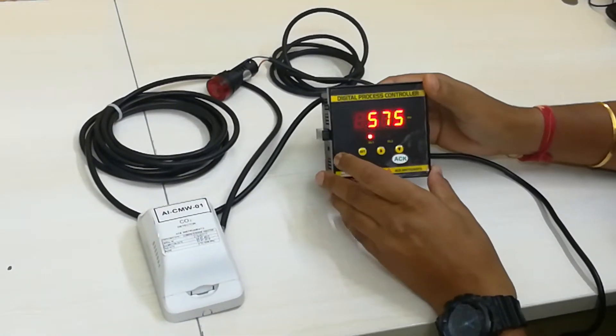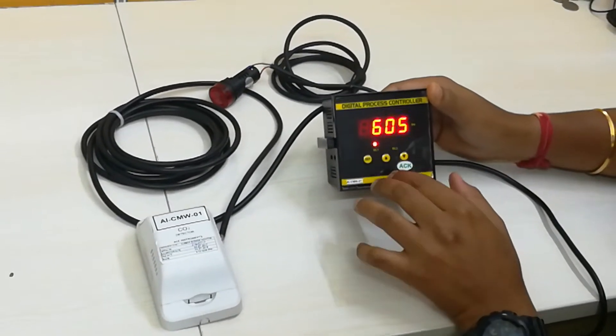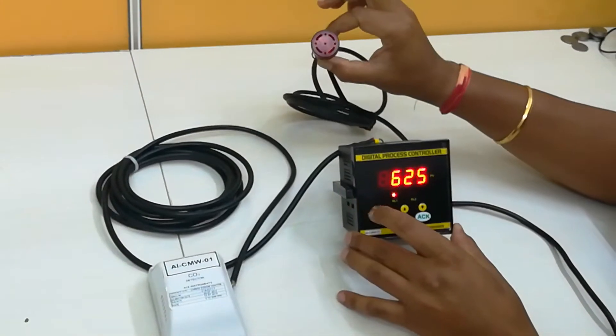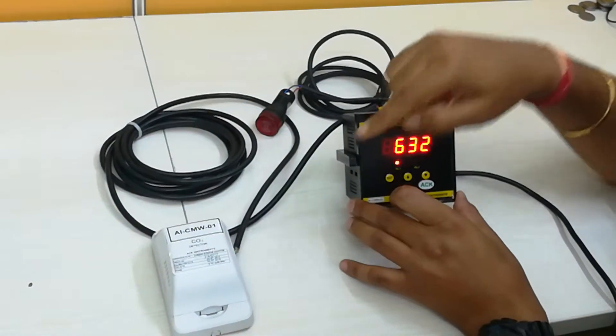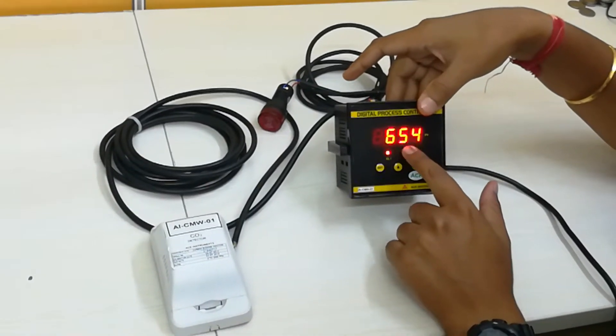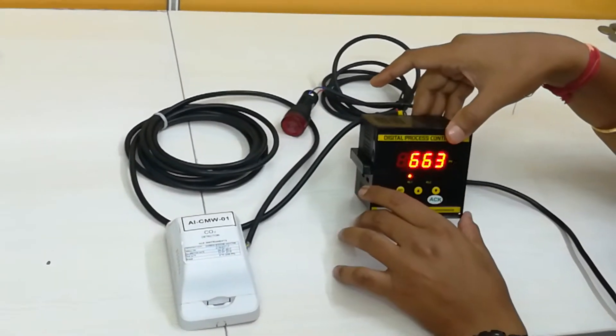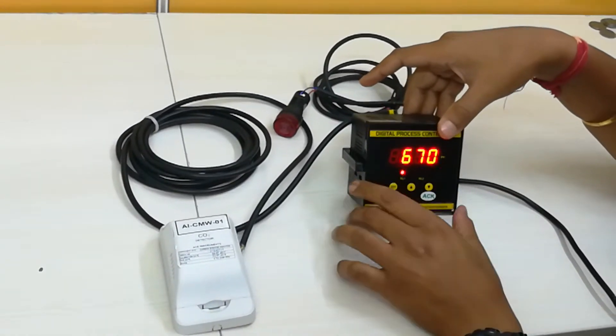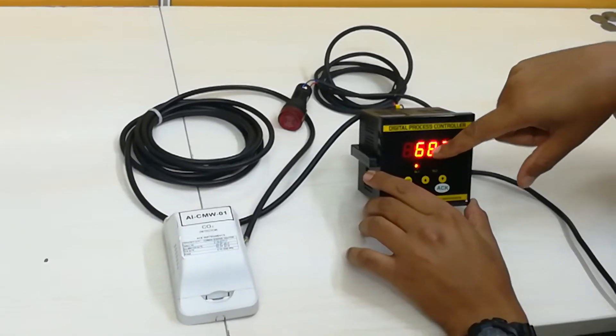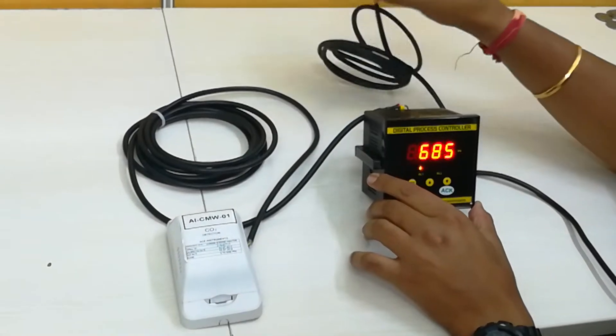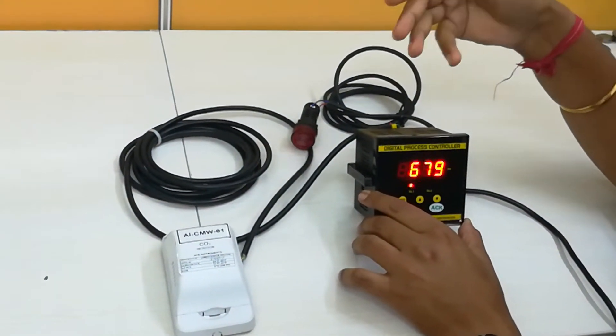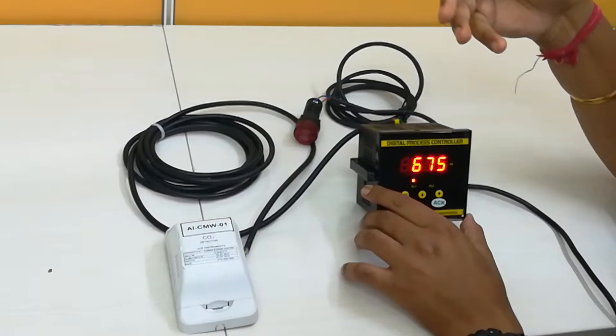This is the digital process controller which has the program logic which can control any external instrument based on the values coming from the carbon dioxide transmitter. As you can see this is showing the current ppm level which is 665 something like that, and we can set the control set points for controlling external devices like alarm, buzzer, door closer, door opener, exhaust fan, or any other device.